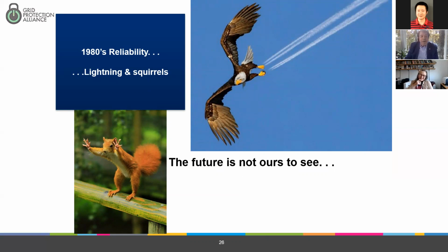With the advent of the VCR and home computers, a momentary outage was no longer acceptable. An outage caused by lightning would reset the clocks on VCRs and cause computers to reboot, and squirrels caused outages on the distribution system. With the metal oxide varistor lightning arresters that we put out on the line, tens of thousands of them, and insulating boots on the 13 kV stingers on the transformers, we pretty much put those two problems to rest, causing very few outages. However, something else was going on.